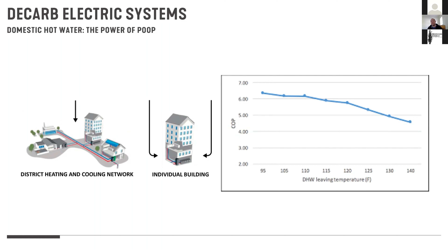That difference is huge. And as I mentioned earlier, when we look at cold climates, if I need a COP of 3, 3.4 year round to show cost parity against fossil gas, then I need to find sources that have a better COP. And so in this case, it's essentially a water source heat pump, the heat exchanger off of the wastewater stream. Now that's not just for domestic hot water. This is a project that I share quite a bit. This is the DC Water headquarters in Washington, DC. In this case, it's a building level system where we're doing all of our heat exchange with wastewater. It's a pressurized wastewater line that runs adjacent to the site.